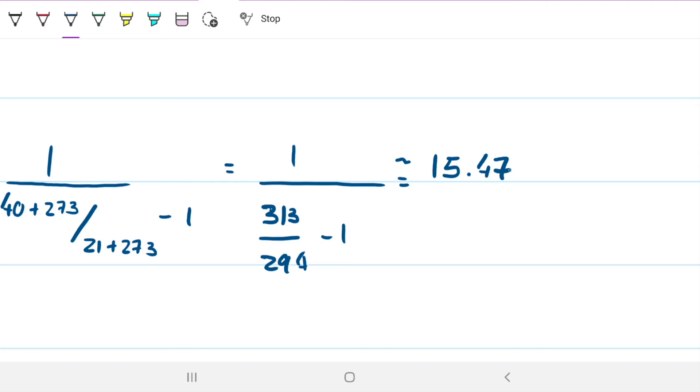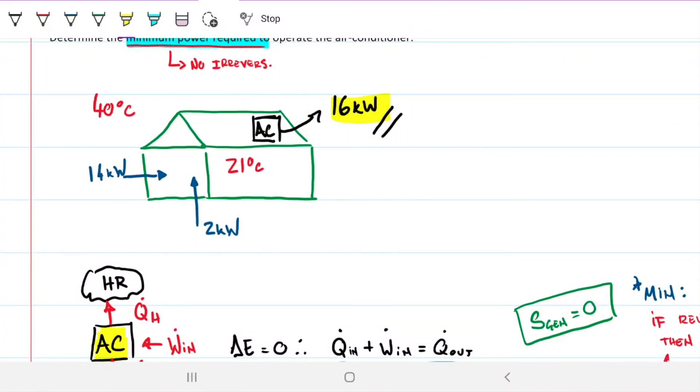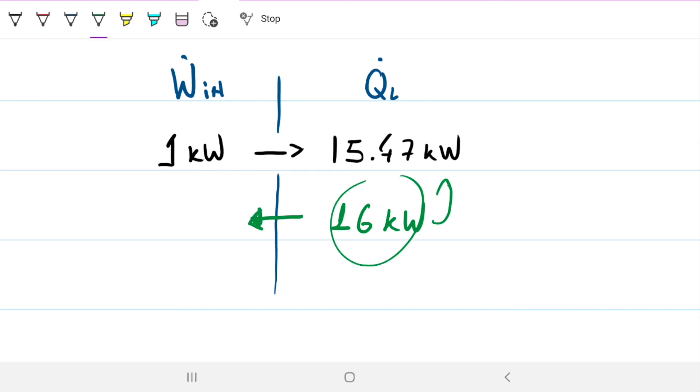And there's no units here because this is the coefficient of performance, the efficiency of it. So what this is saying is that for every 1 kilowatt that I put into this AC, it's going to remove 15.47 kilowatts from my home. So remember that we want 16 kilowatts. So that's actually pretty close to 15.47. So we need to put about 1 kilowatt, a bit more than 1 kilowatt, to make this happen. So for every energy in that I put in here, I'm going to get this Q_L. And if I want to remove 16 kilowatts, what do I need here? Well, I just need to take 16 divided by the 15.47. And that gives me 1.03 kilowatts. That is our answer.